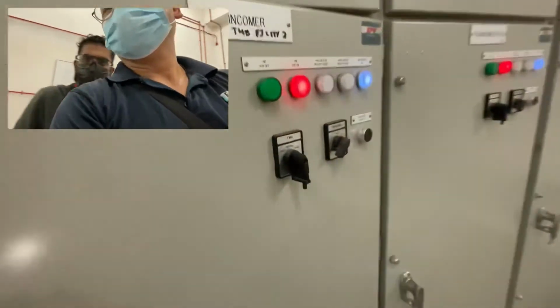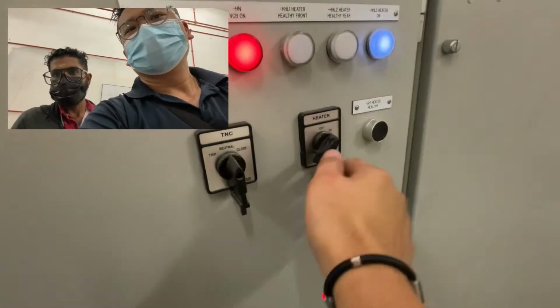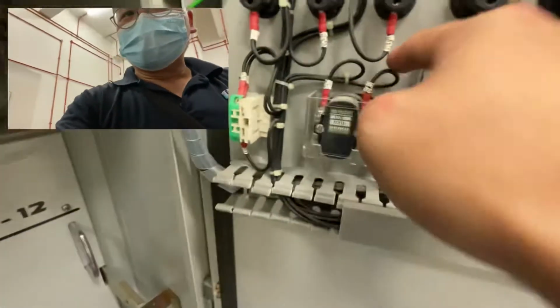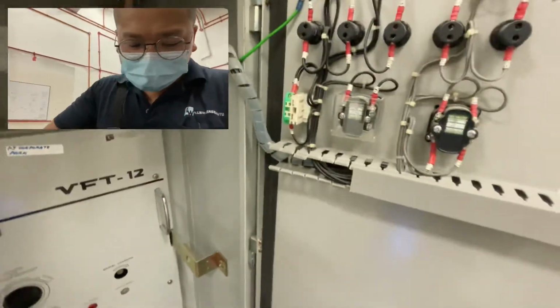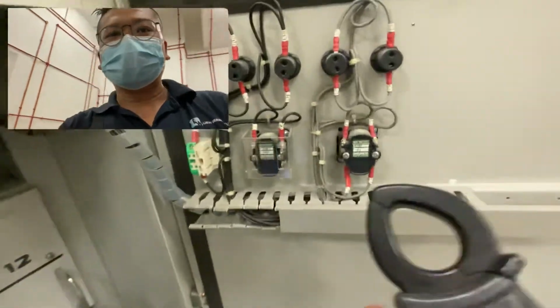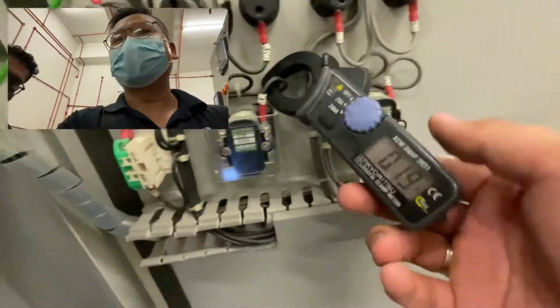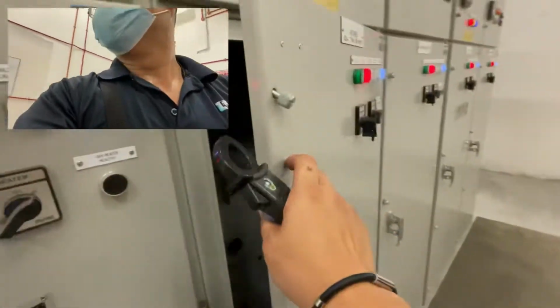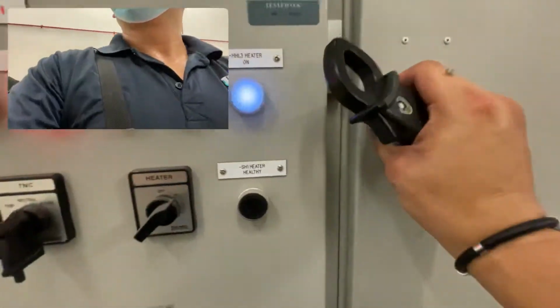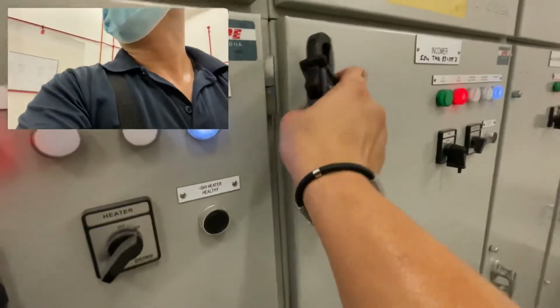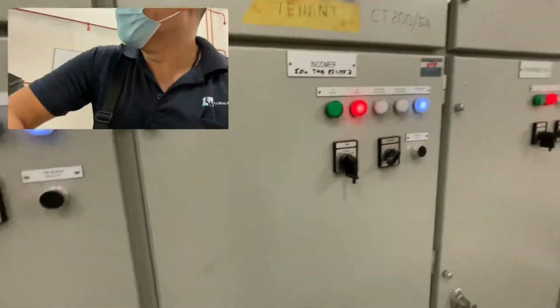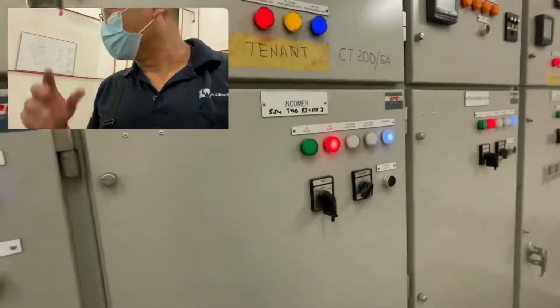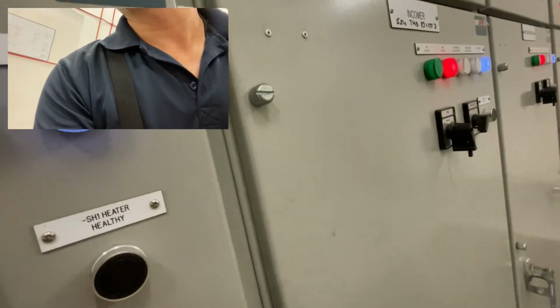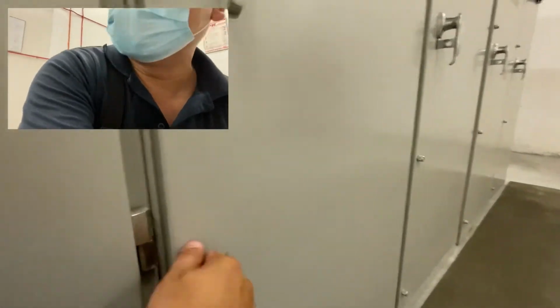Okay, how do we know? You see, this is a heater switch. So there will be current here. As we use a clamp meter and put it there, it will show a reading. See, 0.19. That means the heater is in good condition. Most probably, if your switchgear is more than 10 years old, then mostly the heater will be damaged or faulty. But if the building is just a few years old, seldom does the heater spoil.